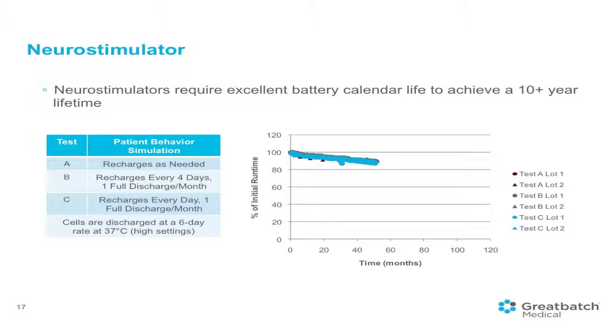And we tried to simulate different patient behaviors by looking at one case where somebody recharges whenever the battery's dead. And I don't know if anybody would do that. Another case where someone recharges every 4 days, no matter what. And another case where somebody recharges every day, no matter what. And we did one full discharge every month so we could see what the maximum runtime would be. And what's interesting is we found that it actually didn't matter very much what you did. Up to this point, we got the same retention up to 5 years.